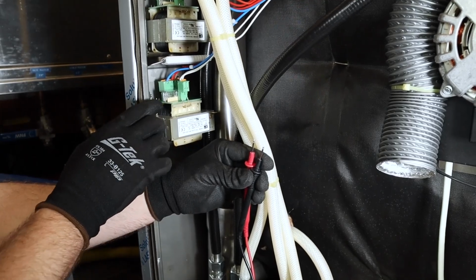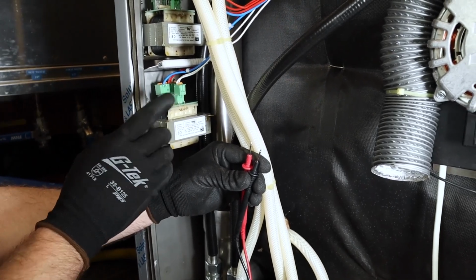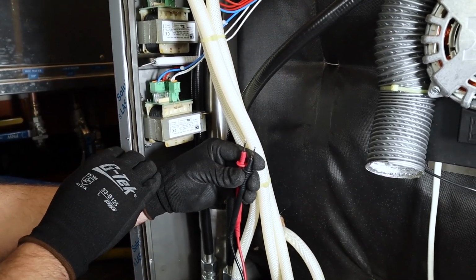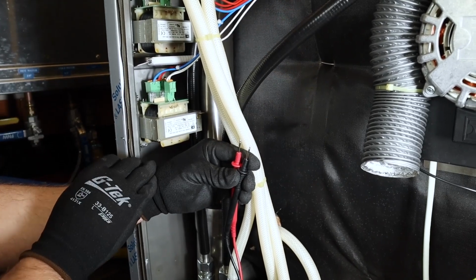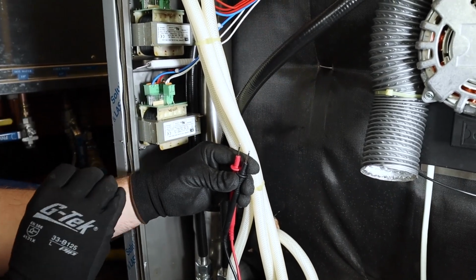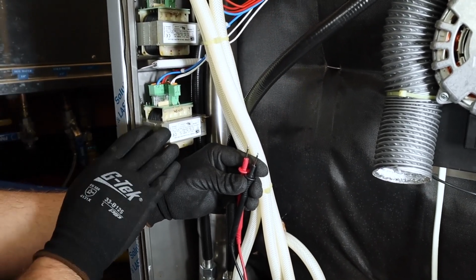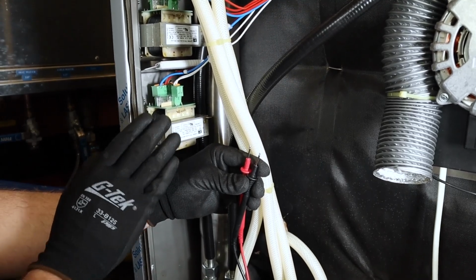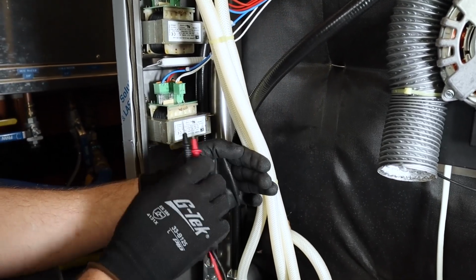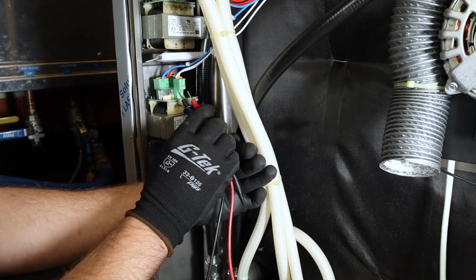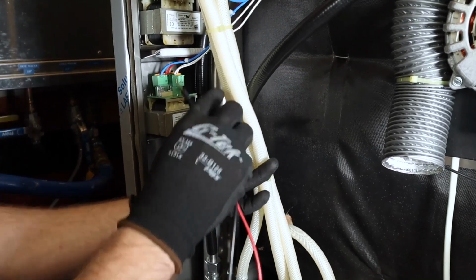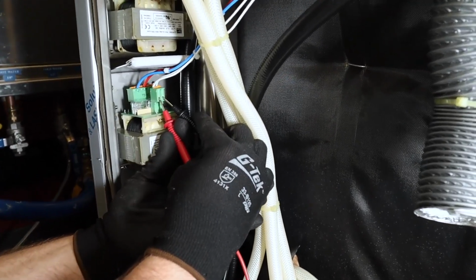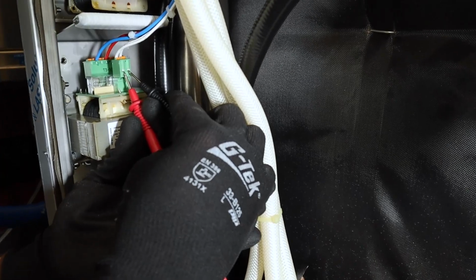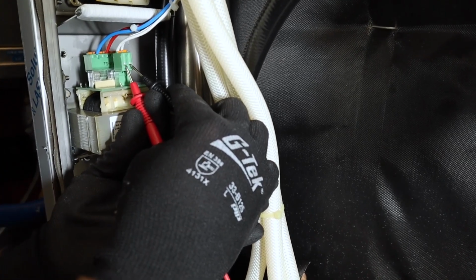One thing to keep in mind, guys, is let's say we're not getting that 24 to 28 volts AC going out to our glow electrode, and keep in mind, we have to start a cook cycle for that voltage to actually ever even be there, and it's only going to be there for a few moments. So if we wanted to check that 24 to 28 volts AC, we would check it right here on these terminals of this connector right here.